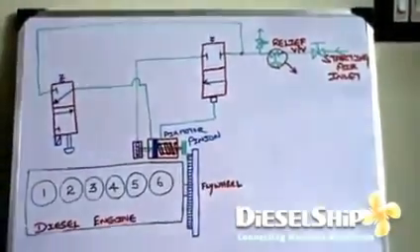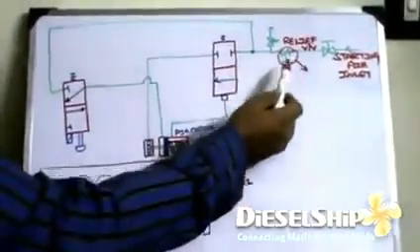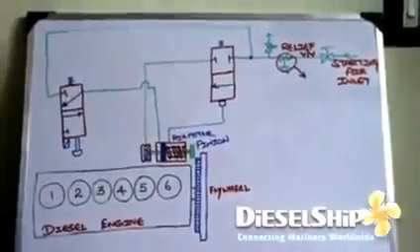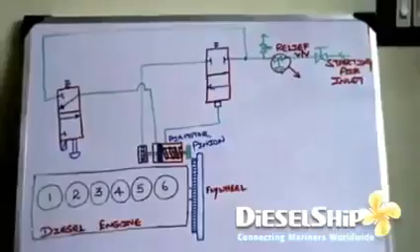For bigger engines, if you want to start with air motor, 30 bar is required. If it's a small engine, 30 bar is not required. So this pressure regulating valve may be adjusted for 20 bar, so it reduces the pressure and then gives to the starting circuit.